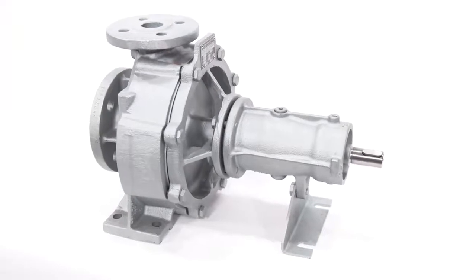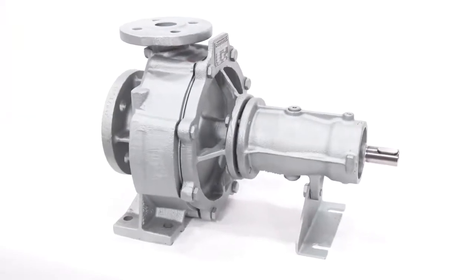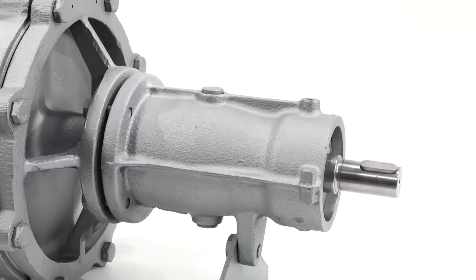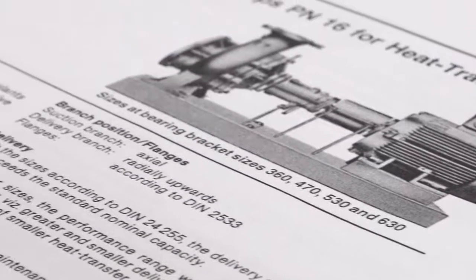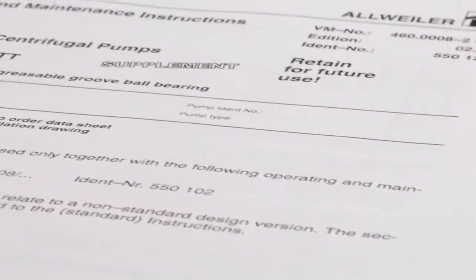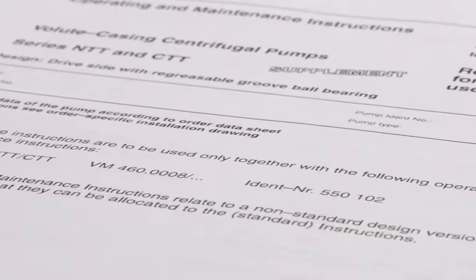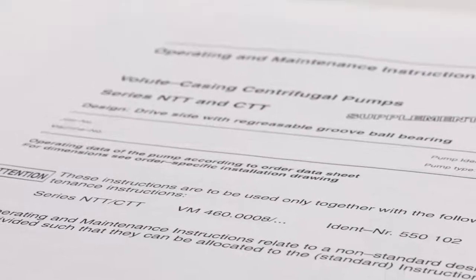Your Allweiler NTT thermal oil centrifugal pump is now fully assembled. Be sure to slowly fill and vent the bearing housing with new oil before startup. Check to make sure the pump shaft turns freely. Please follow all leak testing procedures before reinstallation of the Allweiler NTT series pump to ensure that the pump will not leak. If no leaks are present, the pump can now be reinstalled into the pump system.